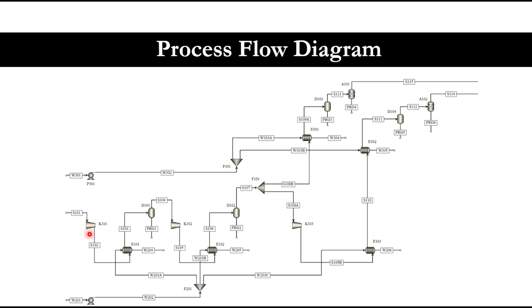It starts from compressor K-101 in this diagram. The feed is compressed and then cooled down in a heat exchanger, which is usually a shell-and-tube heat exchanger. The cooling media is cooling water supplied from a cooling tower. You can see this is a three-stage compression system — this is the first stage, this is the second stage, and the next one is the third stage.